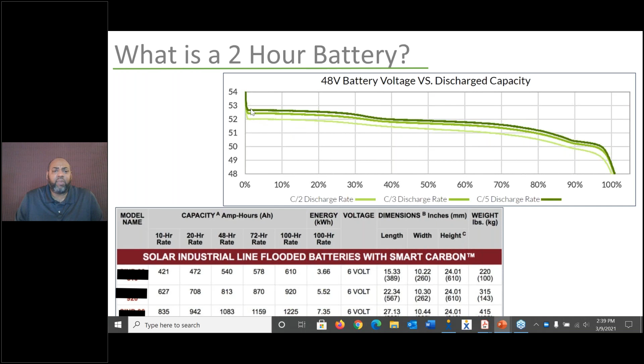So the next principle, which correlates to the first one, is the 2-hour sizing principle. This is very, very, very important. So what does this mean? If you were to take the 18.5 kilowatt-hour battery and divide it by an 8 kW inverter, that math works out to be 2.31 hours. So a little less than 2.5 hours to discharge this battery. So when you're designing a battery, because lithium is designed around 2 hours, you basically want to make sure that you're not undersizing the system. Sometimes people design the battery, they want to get the biggest inverter and they want to get the smallest battery.